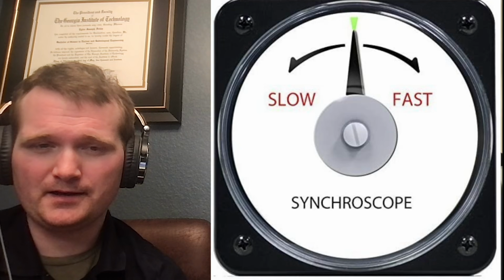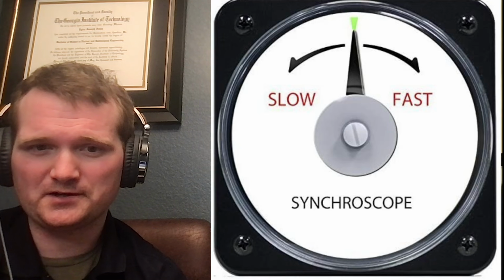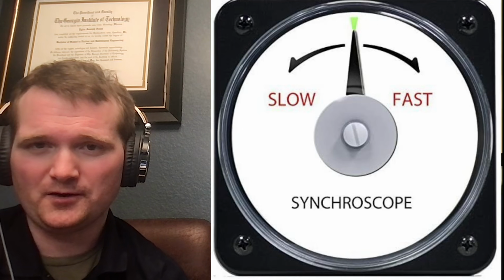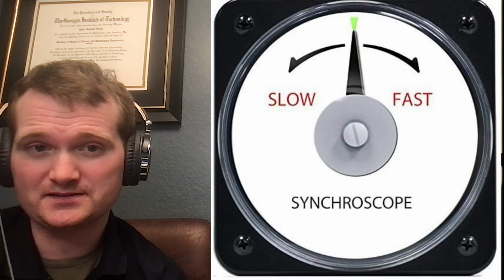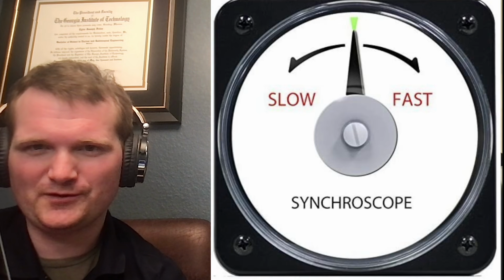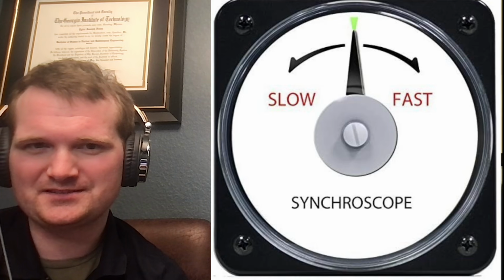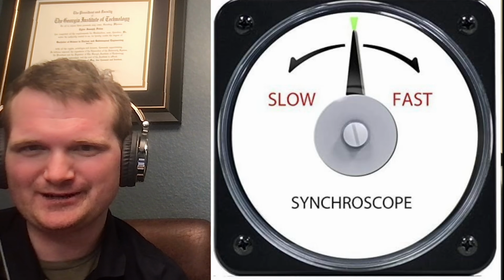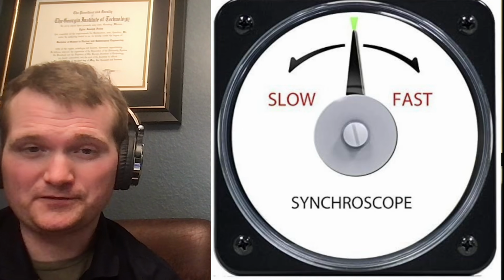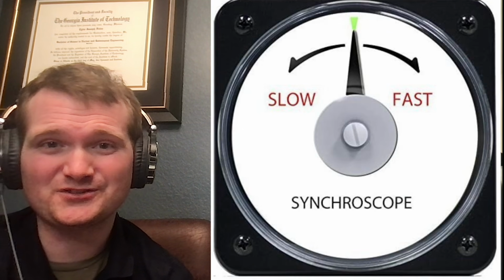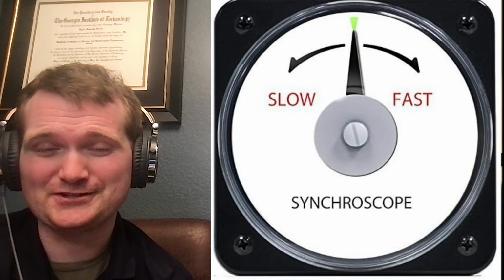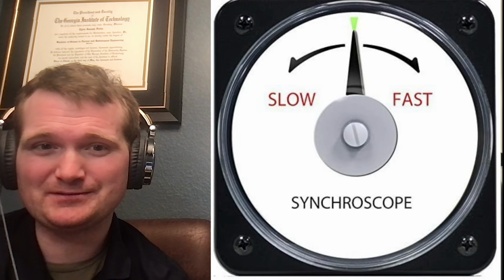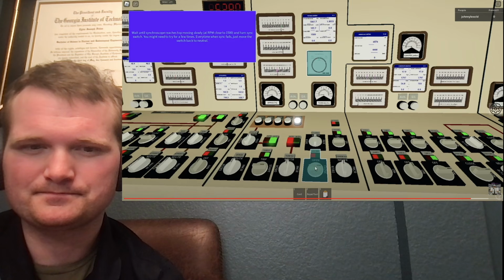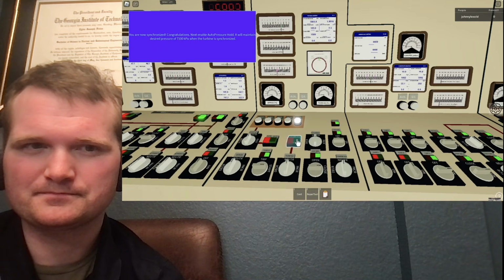This thing's going to be moving, and you're going to want to close the main generator output breaker, which syncs the generator to the grid, when the needle is moving slowly in the fast direction, so clockwise. And there's a bit of a delay. So if you imagine this as a clock, I was always taught to close it at 11:55 with straight up being noon. If you were at 6 o'clock or straight down, where you're 180 degrees out of phase with the grid, that's bad. You're going to break your generator. Do not break your generator. Those things are expensive. Well, that looked pretty easy and anticlimactic.